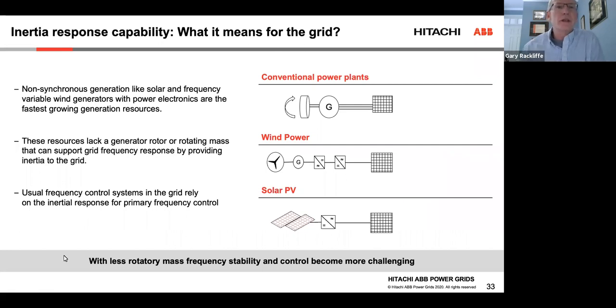So just a little bit more detail on the inertia response capability, and what does this mean for the grid? Conventional thermal power plants like coal and nuclear have a rotor associated with that generation, which provides inertia to the grid. It decreases the speed at which the frequency decays when there is a grid disruption. The challenge is with generation resources that are connected to the grid through power electronics, you don't get that contribution to inertia, which means the grid is more susceptible to disturbances.